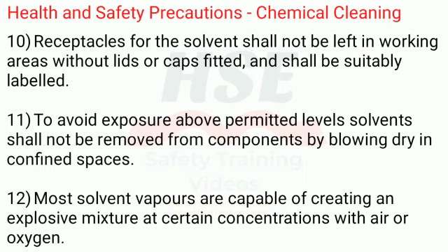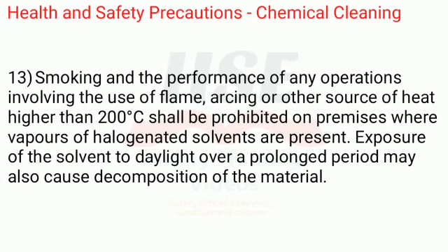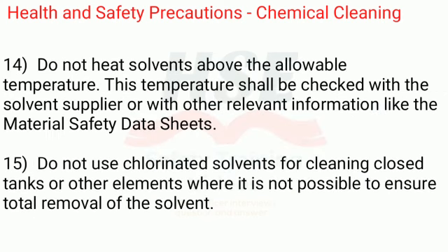12. Most solvent vapors are capable of creating an explosive mixture at certain concentrations with air or oxygen. 13. Smoking and the performance of any operations involving the use of flame, arcing or other source of heat higher than 200 degrees Celsius shall be prohibited on premises where vapors of halogenated solvents are present. Exposure of the solvent to daylight over a prolonged period may also cause decomposition of the material.